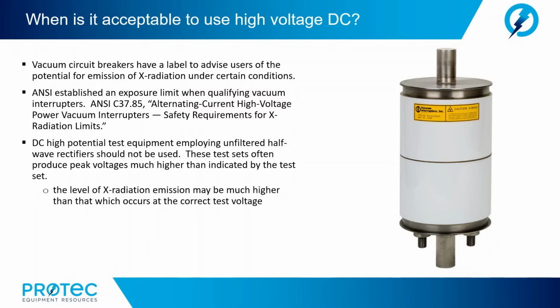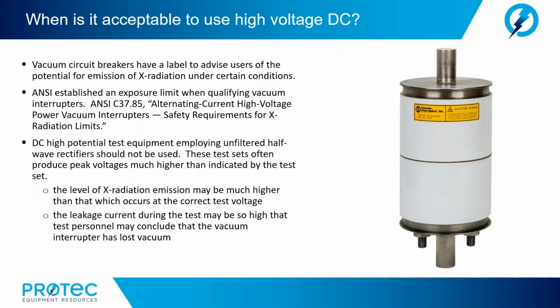First, and most important, the level of X radiation emission may be much higher than that which occurs at the correct test voltage. Second, the leakage current during the test may be so high that test personnel may conclude that the vacuum interrupter has lost vacuum, when in fact it has not. For these reasons, DC high potential test devices using half-wave rectification should never be used for testing of vacuum interrupters.